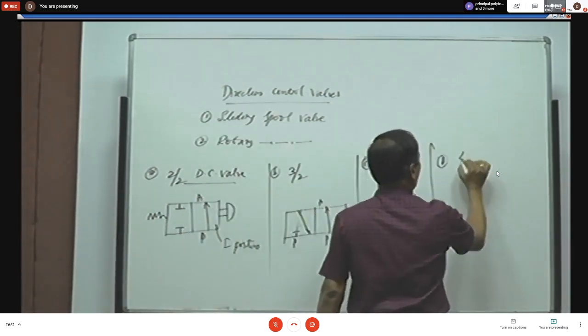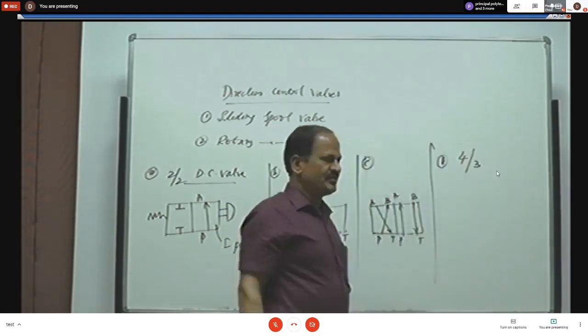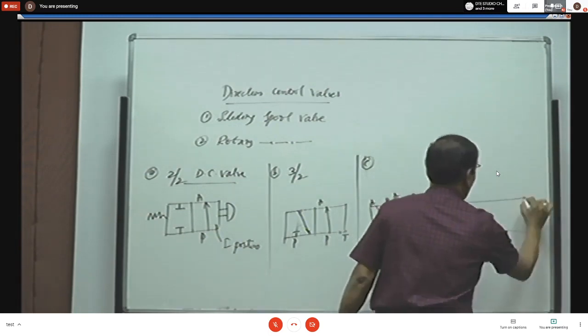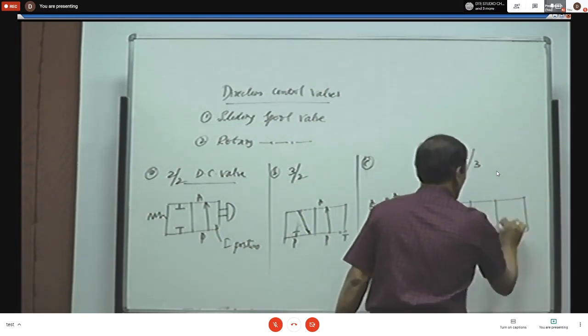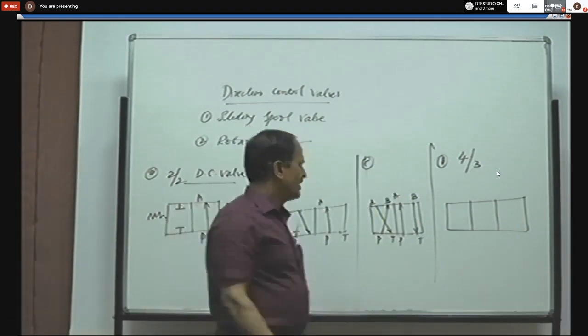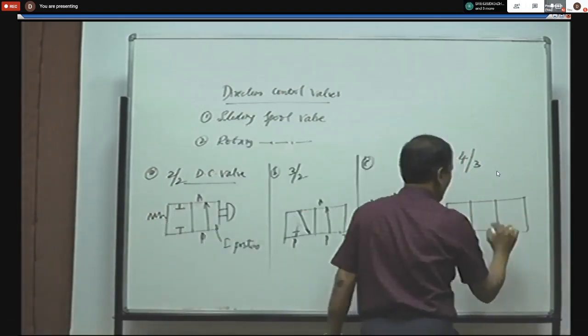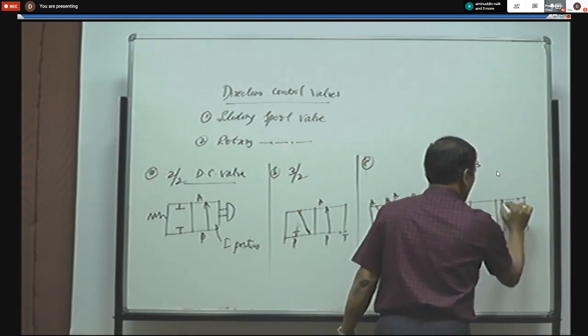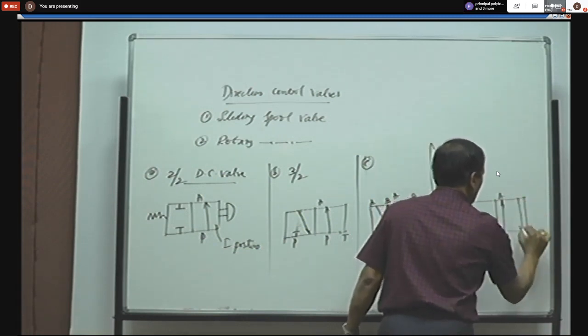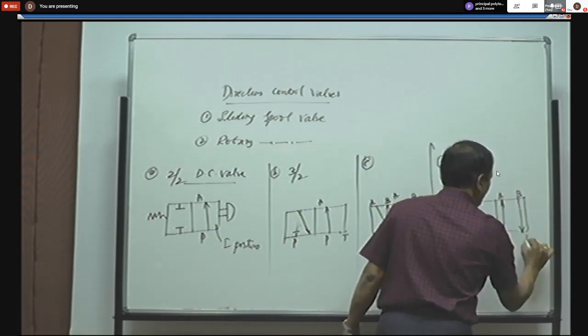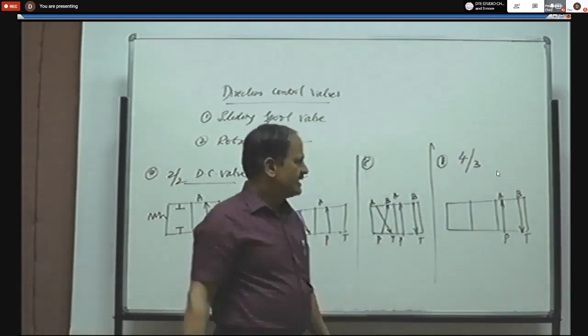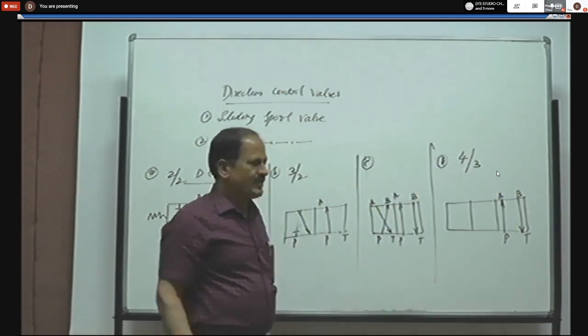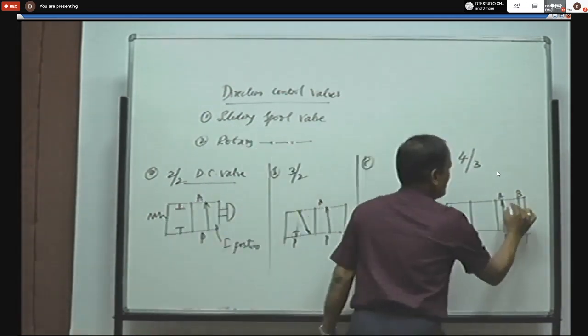In the case of the 4x3 DC valve, there are three positions, represented by three boxes. In the first position, P is connected to A and B is connected to T — the extension of a cylinder takes place. In the second position the direction of flow is reversed: fluid flows from P to B and returns from A to T.